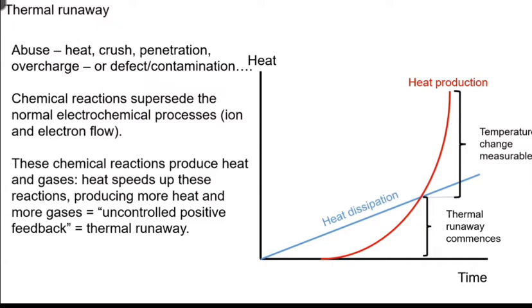Now, when those two lines cross, you will see a measurable temperature rise, and that's the easiest, simplest definition of thermal runaway: from 1 degree centigrade rise per second to 1 degree centigrade rise per minute. But a far better, more accurate definition is when those exothermic, heat-producing chemical processes become self-sustaining and you enter uncontrolled positive feedback. And that almost certainly occurs before those lines cross. At that point, essentially, you can't stop it.